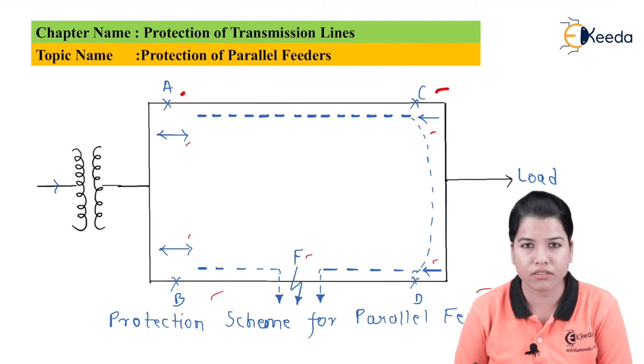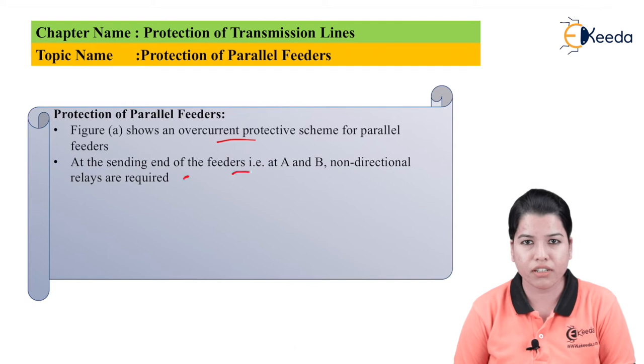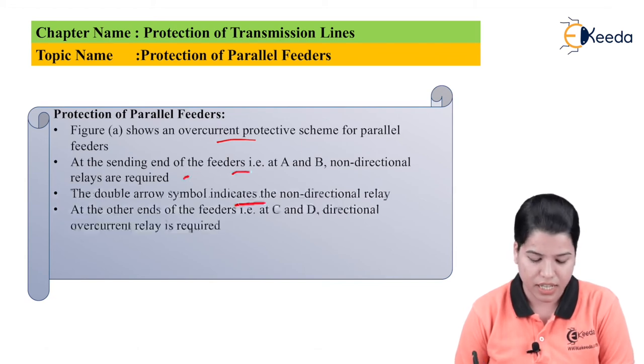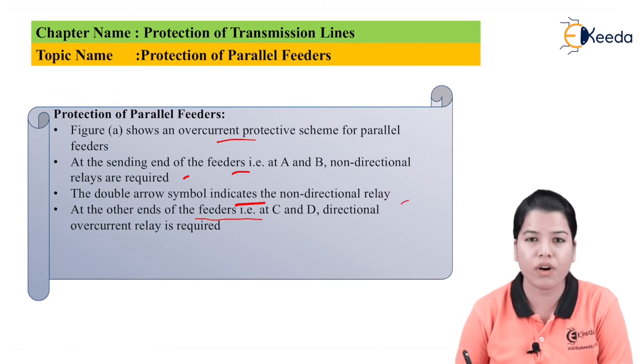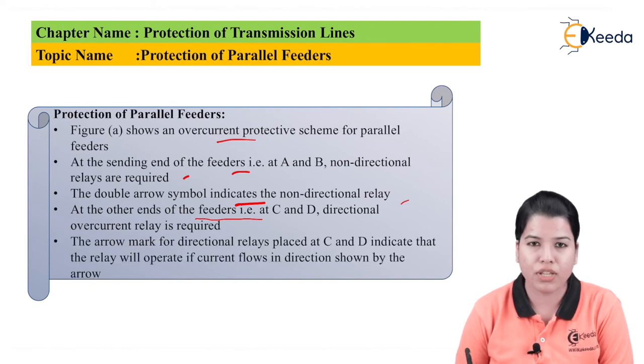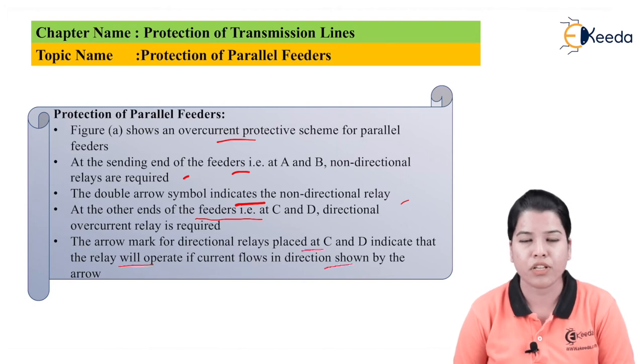Now let us see the working. At the sending end of the feeder, that is at A and B, the non-directional relays are required. The double arrow symbol indicates the non-directional relay. At the other end, that is at sections C and D, the directional overcurrent relay is required, indicated by the single direction arrow. The arrow mark for the directional relay at C and D indicates the relay will operate only if the current flows in the direction shown by the arrow; otherwise, the relay will remain inoperative.